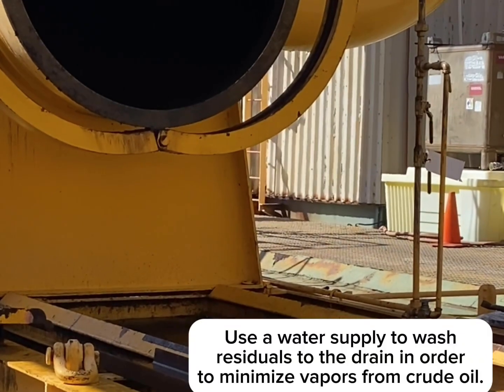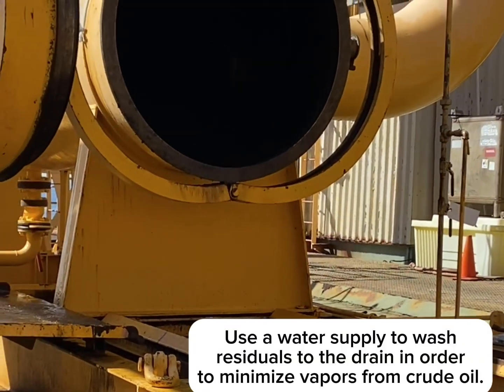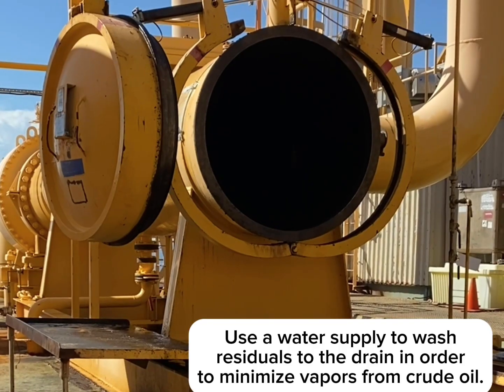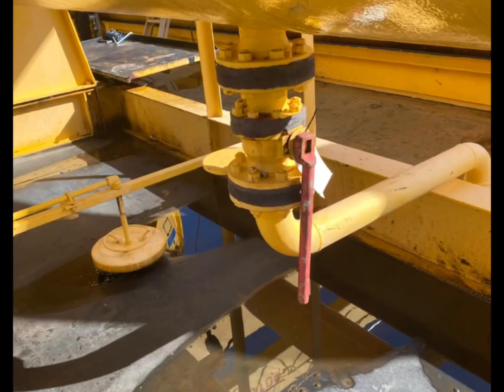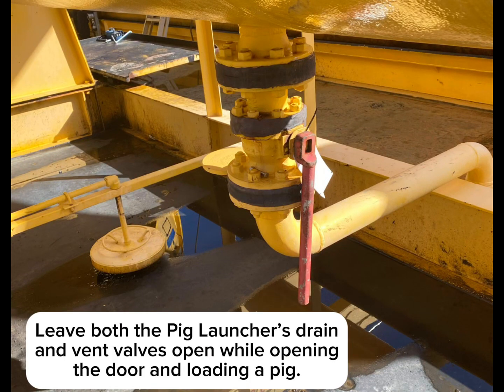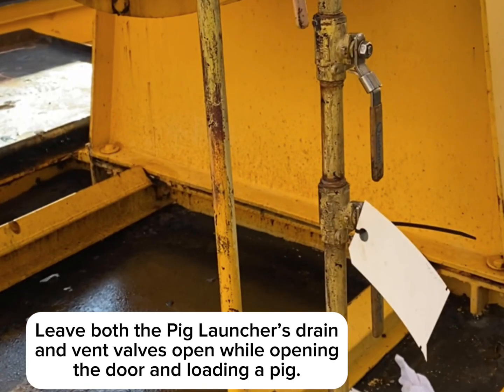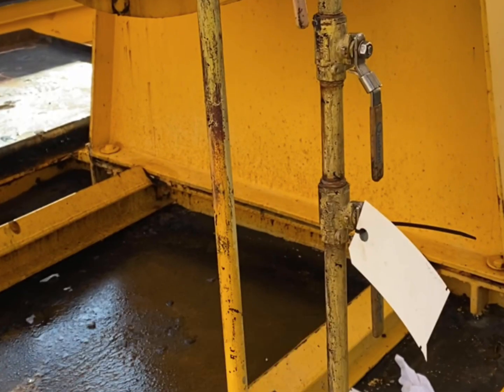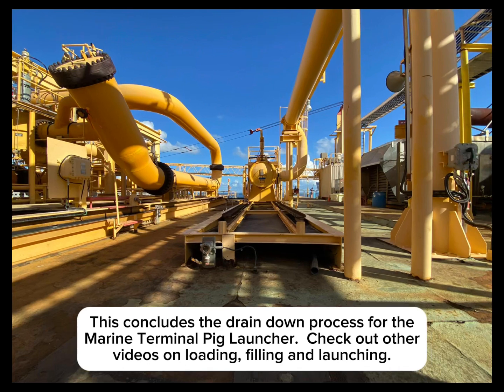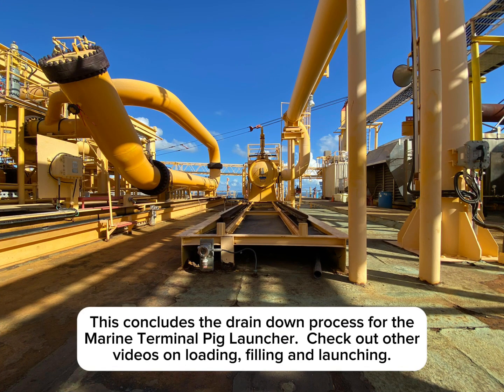Use a water supply to wash residuals to the drain in order to minimize vapors from crude oil. Leave both the pig launcher's drain and vent valves open while opening the door and loading a pig. This concludes the drain down process for the Marine Terminal Pig Launcher.